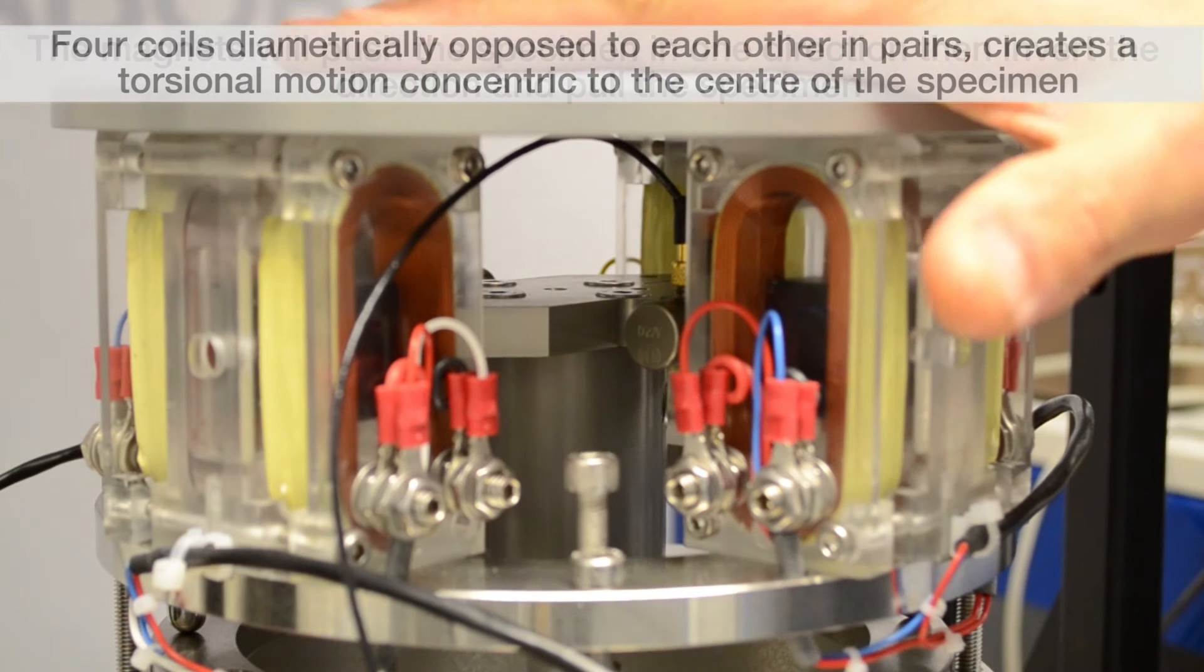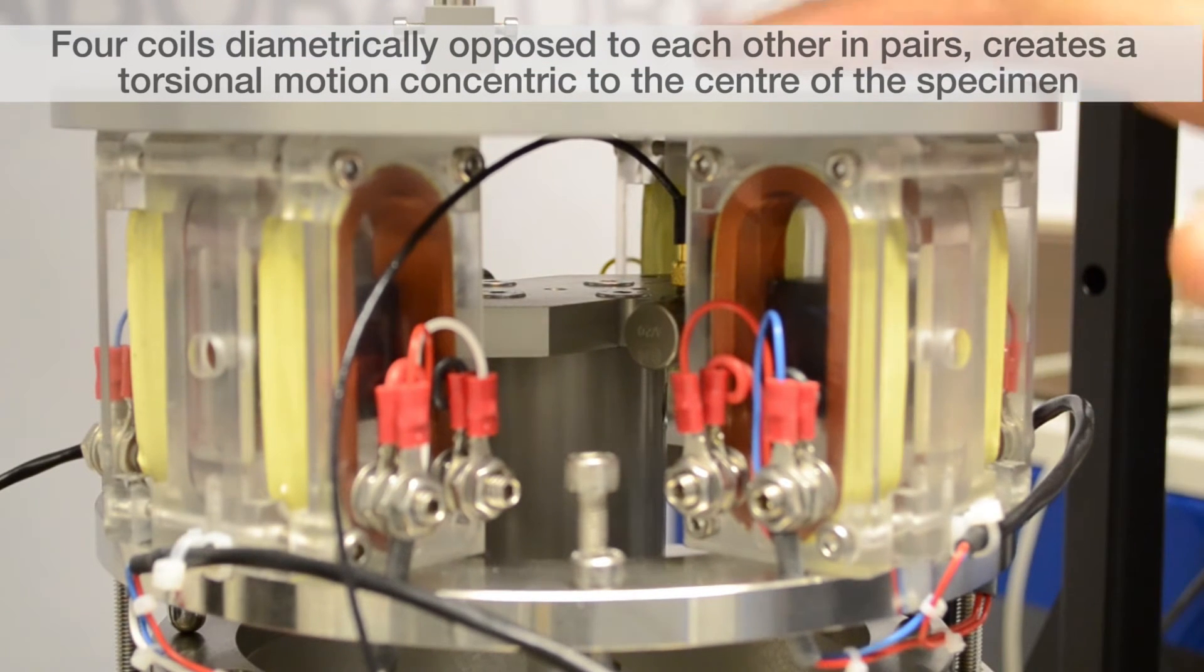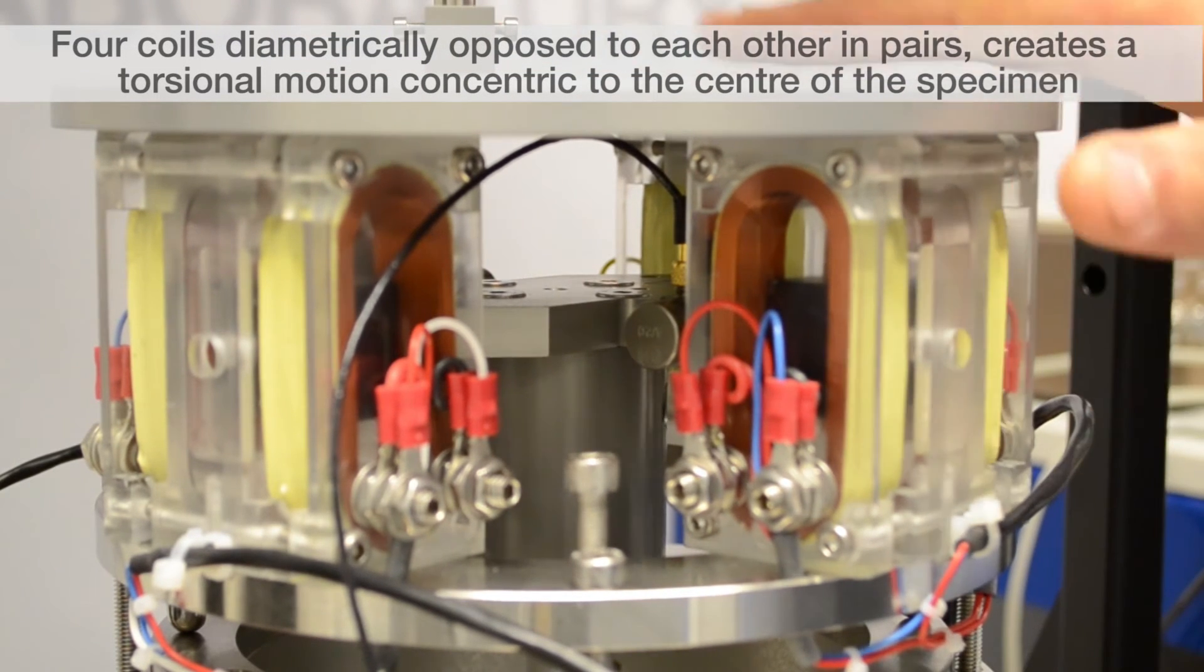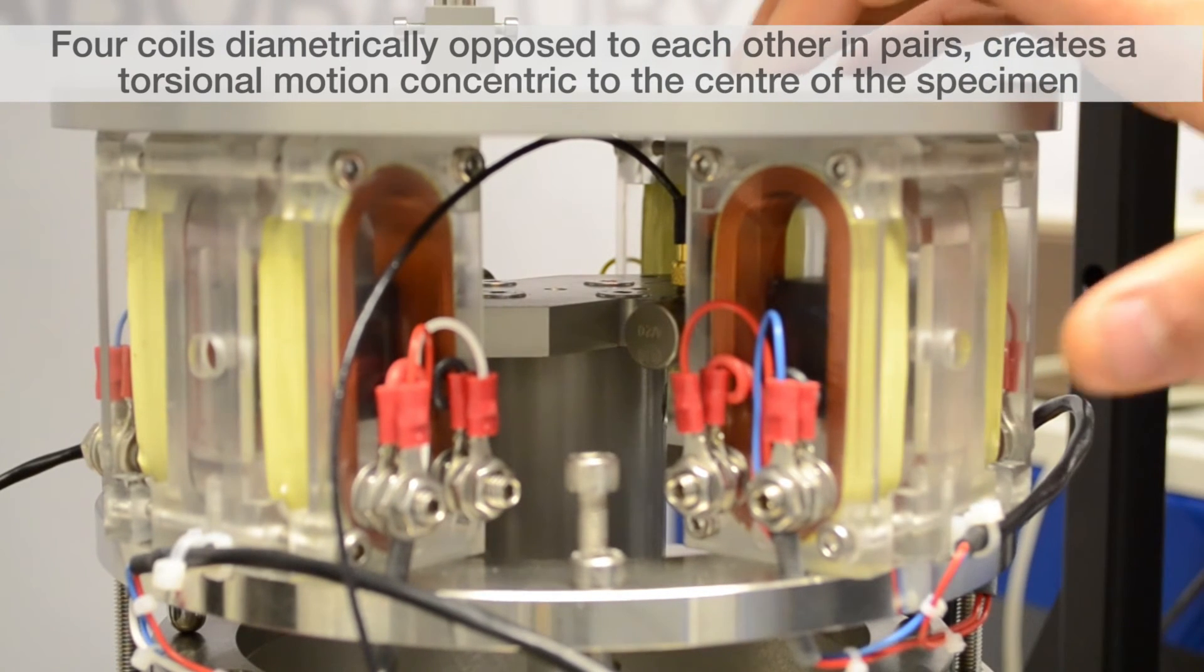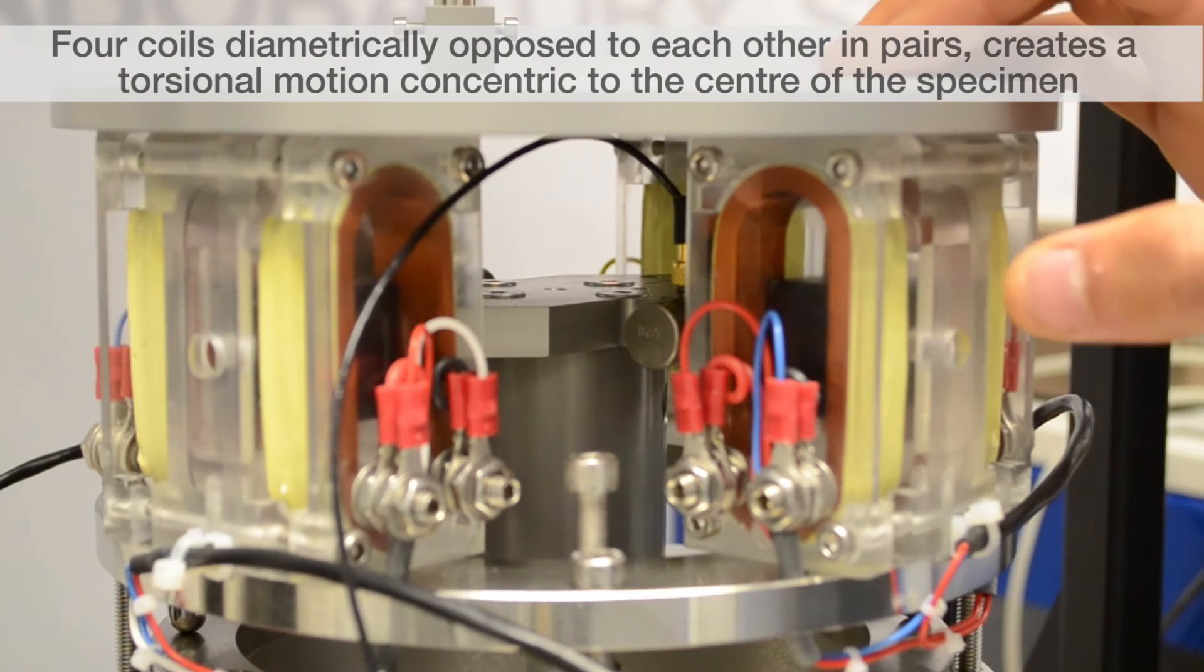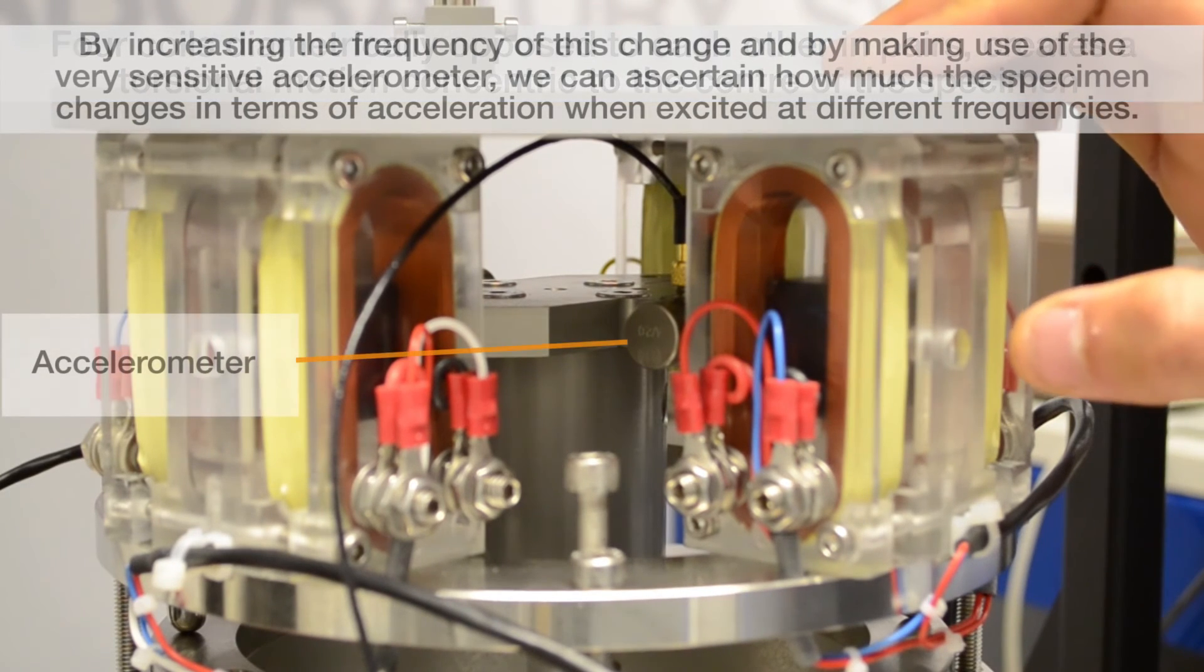By having four coils diametrically opposed to each other in pairs, what we have is a torsional motion that's concentric to the center of the specimen.